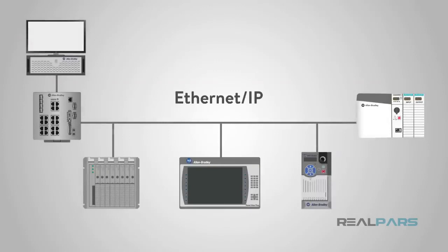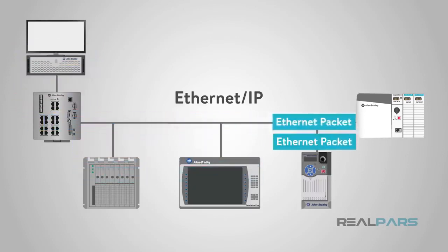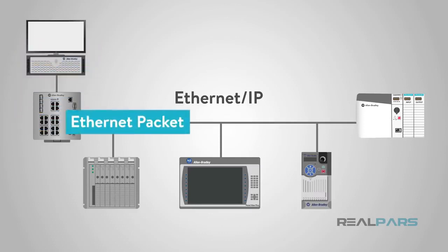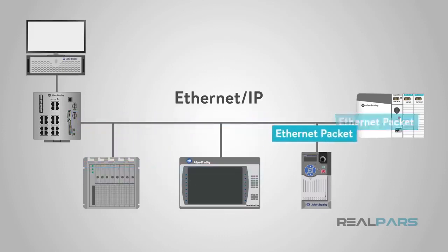This EIP is compatible with many standard Ethernet switches used within the industrial automation arena, which makes it easy to implement. Combinations of data speeds of 10 or 100 megabits per second are easily handled with these off-the-shelf switches. In the simplest terms, Ethernet IP is Ethernet packets used with the industrial protocol of CIP, TCP/IP, and UDP layers to provide the required data to your controller.